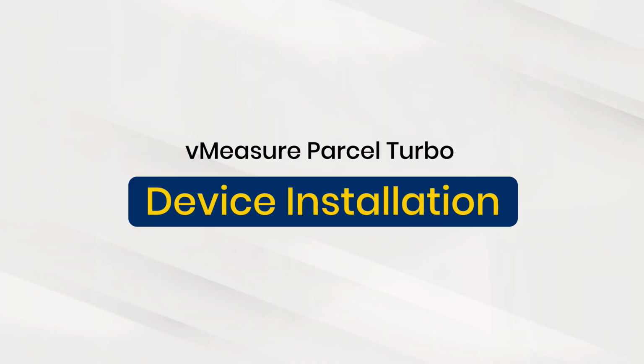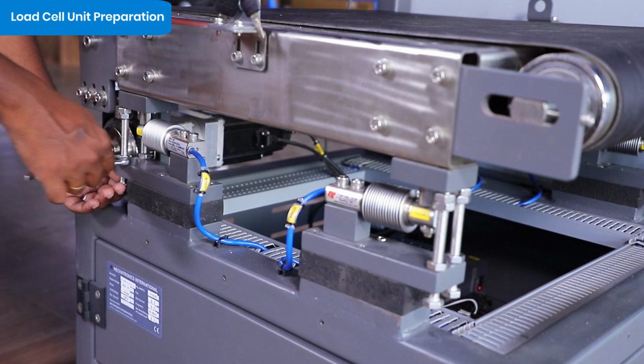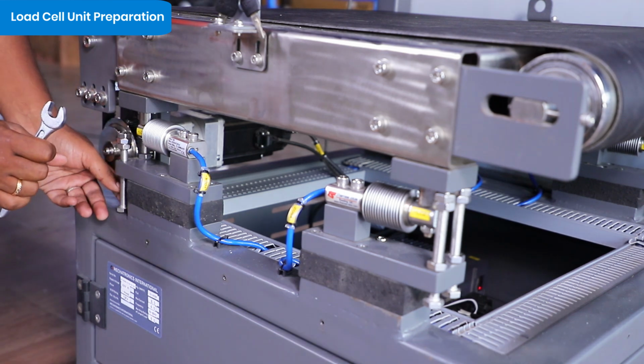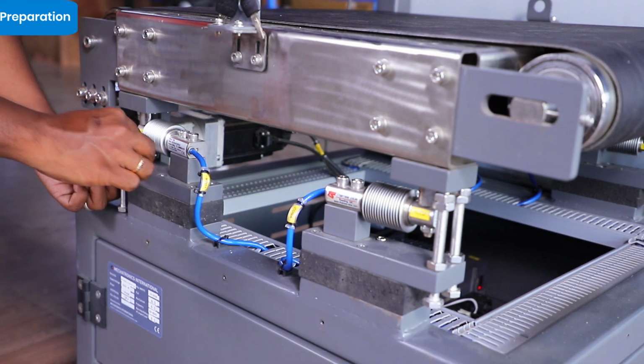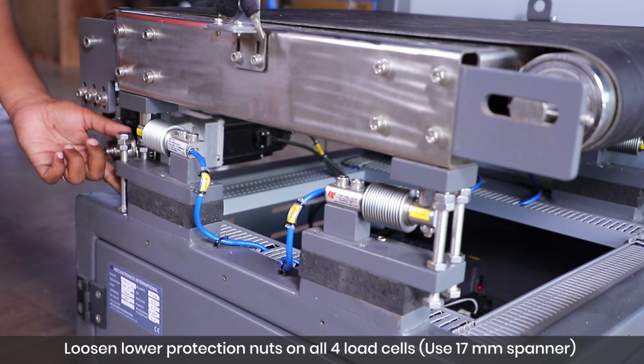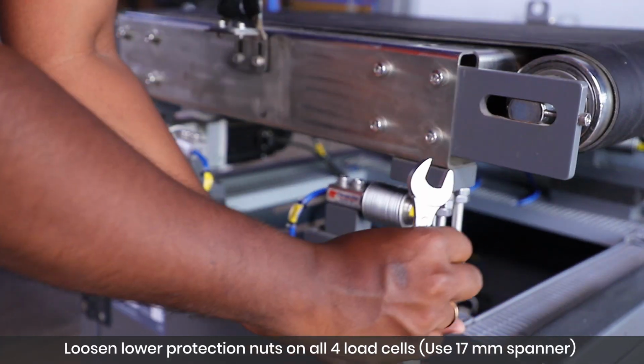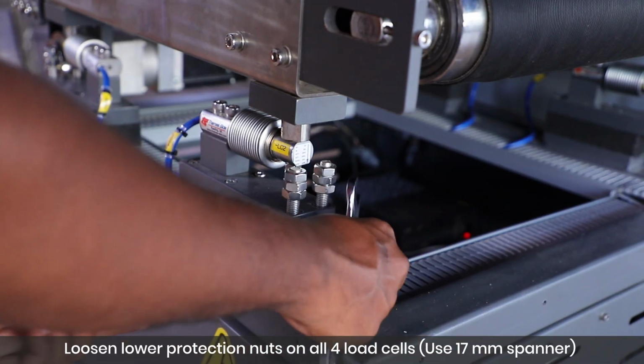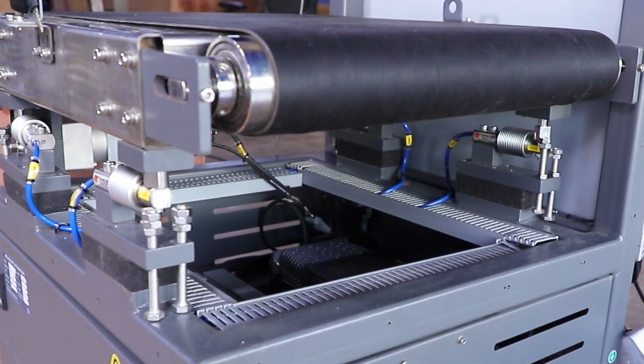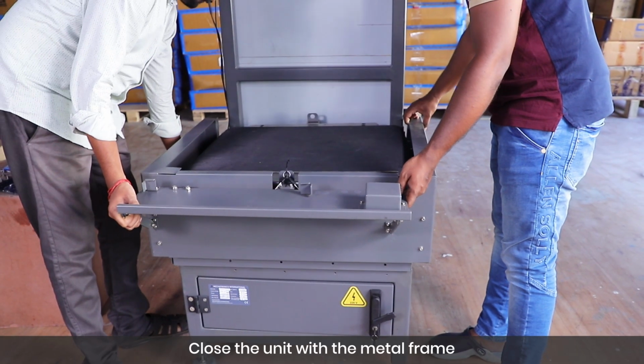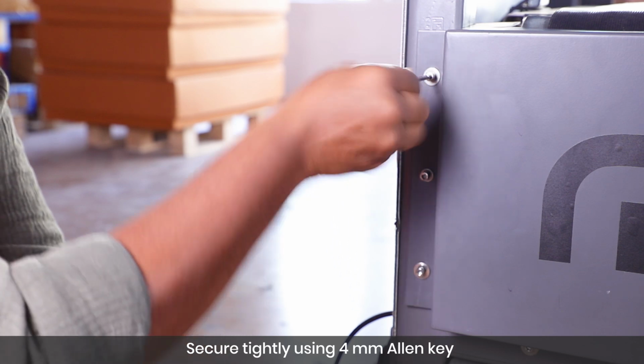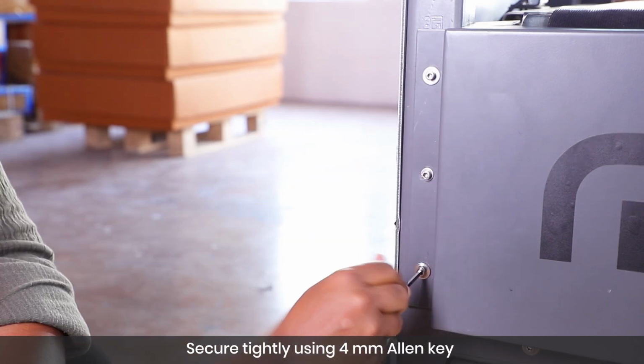Next, begin installing the device. First, prepare the weighing scale. The pre-assembled load cell unit is kept tight to prevent damage during transit. Using a 17mm spanner, loosen the lower protection nut on each of the 4 load cells. After loosening all 4 corners, place the provided metal frame over the load cell unit and secure it tightly using a 4mm Allen key.